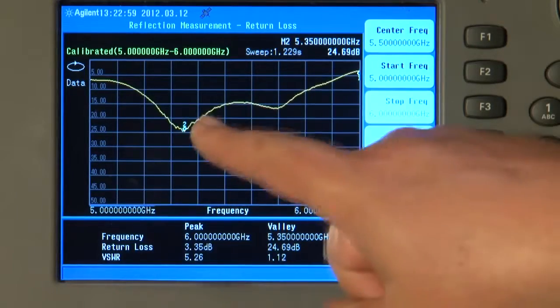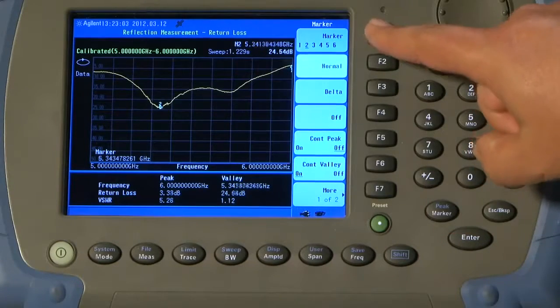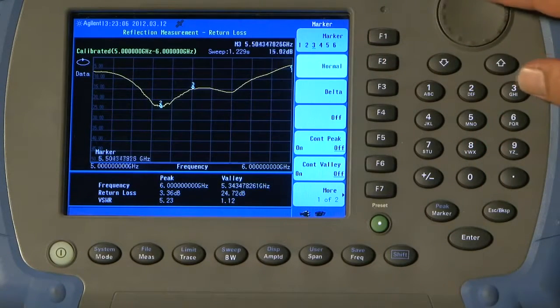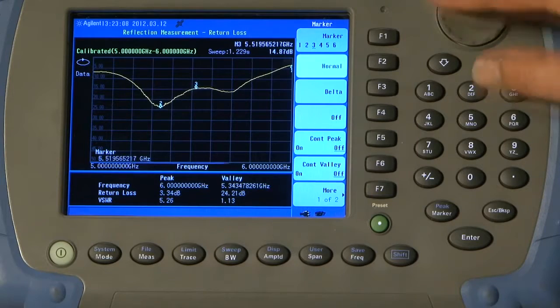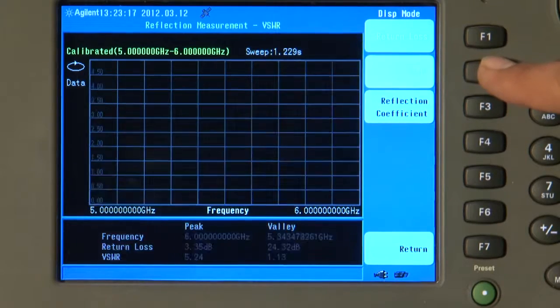We can move these markers manually if we wish, or add more markers by pressing the Marker button. I could turn on Marker 3, and I can move that with the knob. Also, if I press the Measure button, instead of displaying return loss, we can measure and display VSWR.